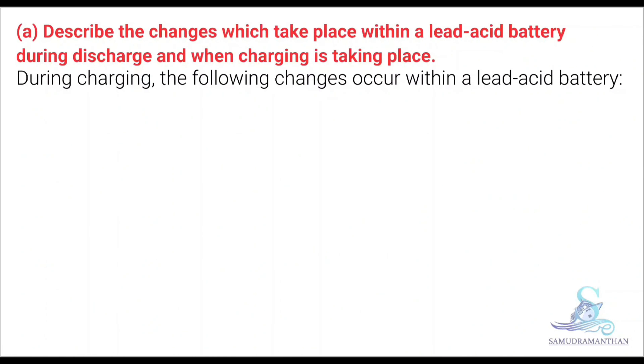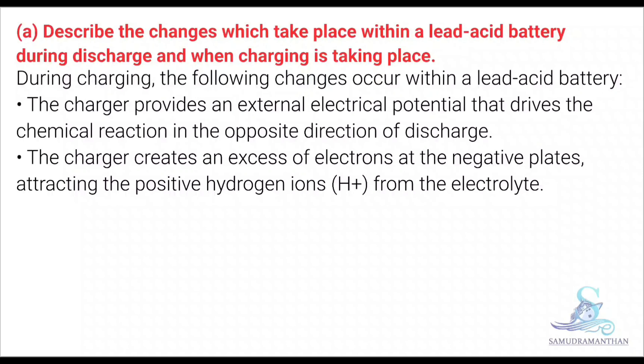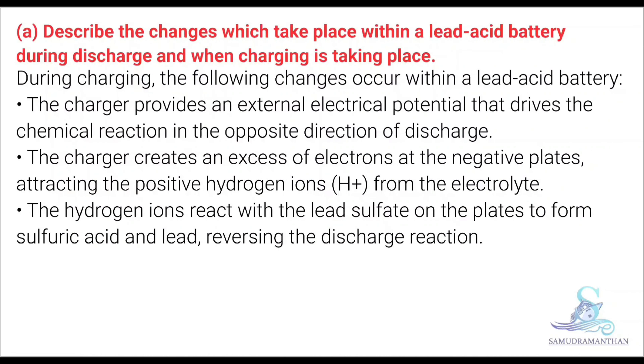Now we will discuss the charging process. During charging, the following changes occur within a lead acid battery. The charger provides an external electrical potential that drives the chemical reaction in the opposite direction of discharge. The charger creates an excess of electrons at the negative plates, attracting the positive hydrogen ions from the electrolyte. The hydrogen ions react with the lead sulphate on the plates to form sulphuric acid and lead, reversing the discharge reaction.